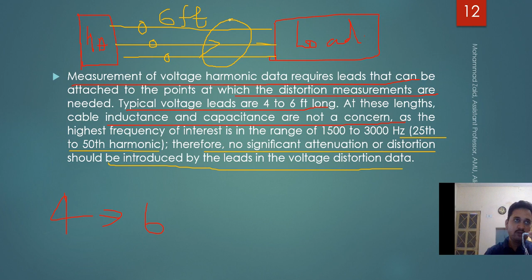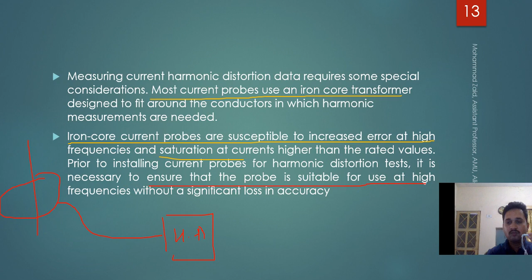Okay, so measuring current harmonic distortion requires some special consideration. Current probes are used for measuring currents. As I already showed you in your previous figure, the current probes are used for measurement of current. But the current probe can also have problems. Iron core current probes are susceptible to error because of what? Saturation. Current probes are just like this: you have a wire going through it, and this is a current probe which may be connected to a harmonic analyzer. Prior to installing current probes for harmonic distortion, it is necessary to test that the probe is suitable at higher frequencies without loss in accuracy.